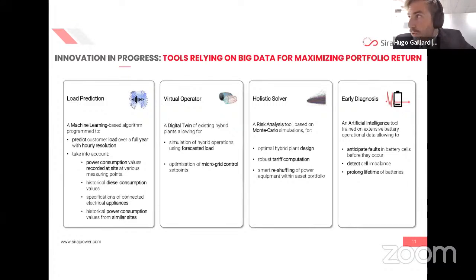Okay, this will allow us to understand what is the seasonality of the load, which allows us to be proactive and maybe to have a different system sizing for winter and for summer. But we actually want to understand it also within a day. So we want to understand if the load demand will be higher during daytime, which actually means that it will be easier to reach a higher penetration because it will be aligned with solar availability. Or to the contrary, if we have maybe some peaks in the evening or at night, which means that we will need to have more storage at site, for example. That allows us to size the system properly.